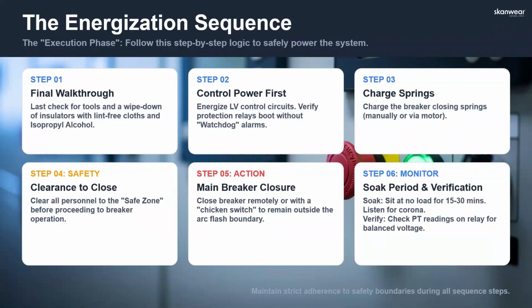Also checking your control power, right? Making sure that your LV control circuits are working, verifying alarms are working. Then you're going to charge your springs to close those breakers, and then closing clearance to close, and then obviously closing that main breaker. Many times, often with medium voltage, you're going to be using tools such as chicken switches so we're keeping the workforce away from that.